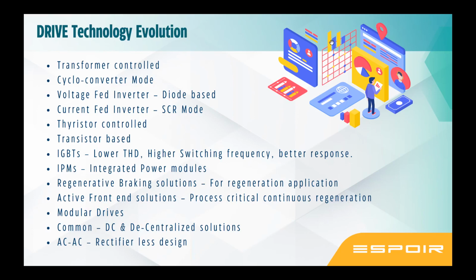IGBTs also have evolved. Nowadays, it comes as a packed model, an integrated power module, meaning the rectifier and inverter sections are both in a single pack. And it is becoming compact, more efficient, with more thermal handling capability. There is a new parallel technology coming as an IGCT, which I will show you some pictures of in the future. Then again, on the application side, the IGBTs with regen options, the active front end, drives have become modular. Then common DC solutions, AC to AC, which is a direct converter, rectifierless designs. So these are the drives that have been coming.